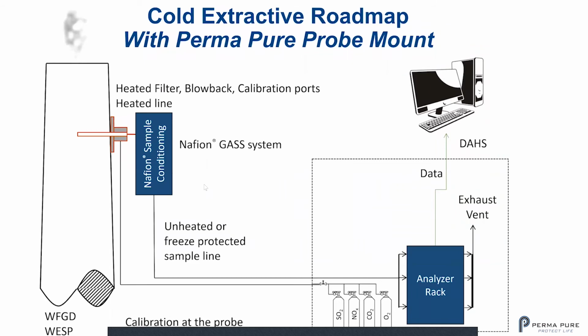Here's a cold extractive roadmap with PermaPure's probe mount. Okay, so here we have our probe mounted on the stack. You have your sample conditioning system right at the probe, in fact, together with the probe. And then from here, you have your unheated freeze protect sample line coming out to your analyzer rack. In this case, the calibration is done at the probe instead, which gives you a much more accurate calibration. The calibration gases are put through the probe and then through the sample conditioner and into your analyzer rack. That's the difference.